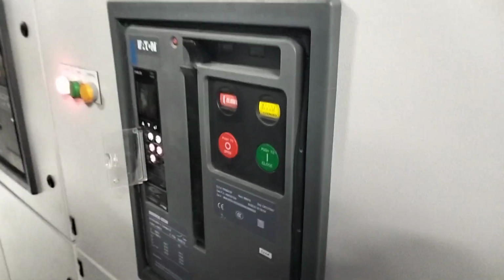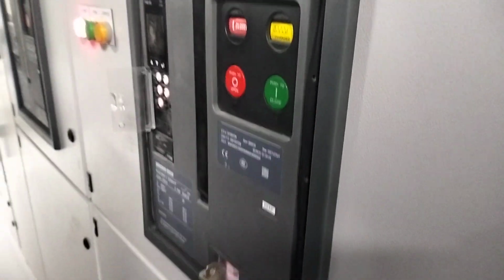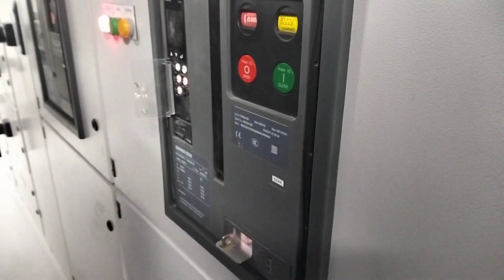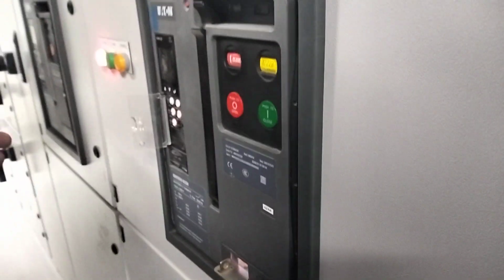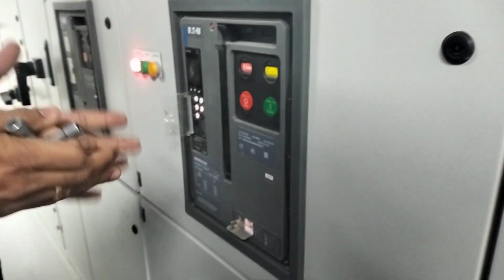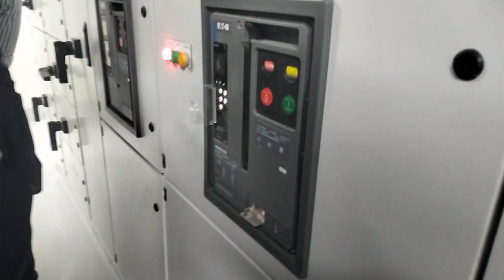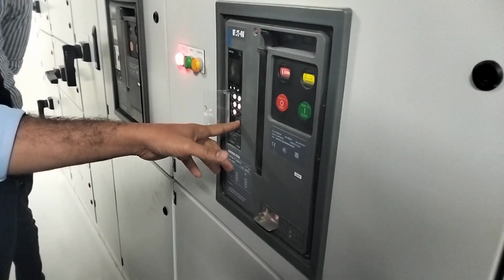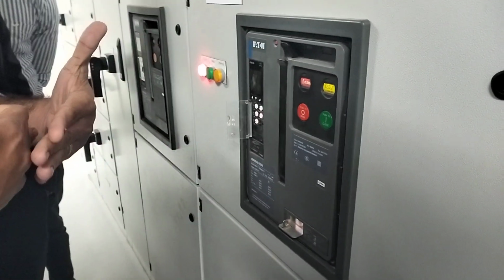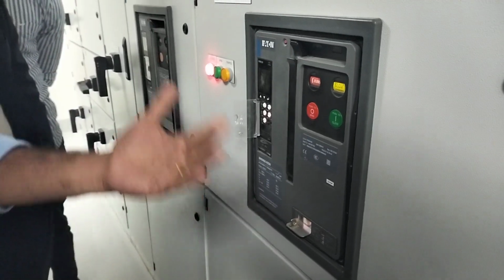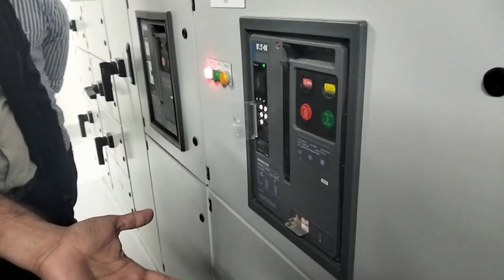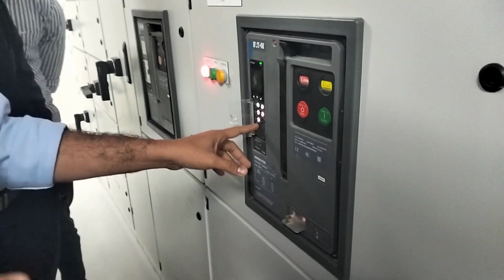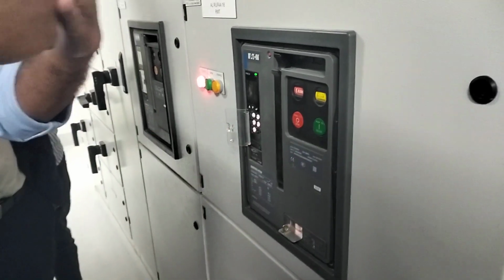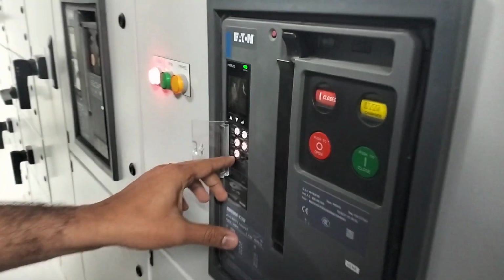I have a question about the breaker safety. We have low voltage and high voltage safety. If there is high voltage, is this your breaker's protection? This PXR20 is the current protection only. Only current protection. So this is overload or short circuit. Short circuit means the current will be in the kilo-ampere rating, like 10,000, 20,000. If there is a short circuit on the cable side, it will probably trip in the instantaneous protection.